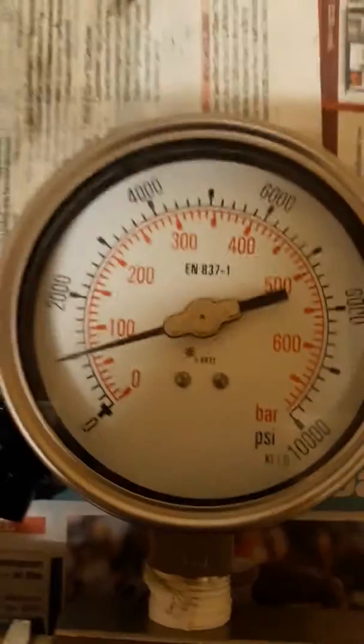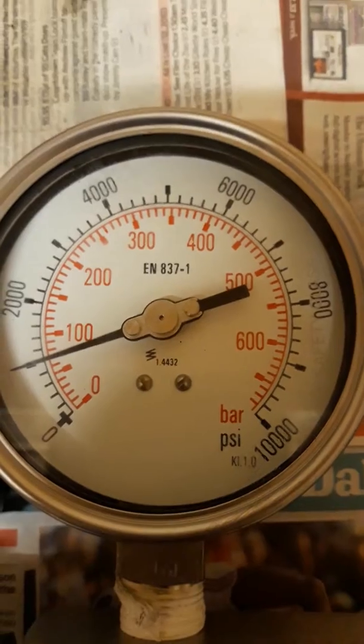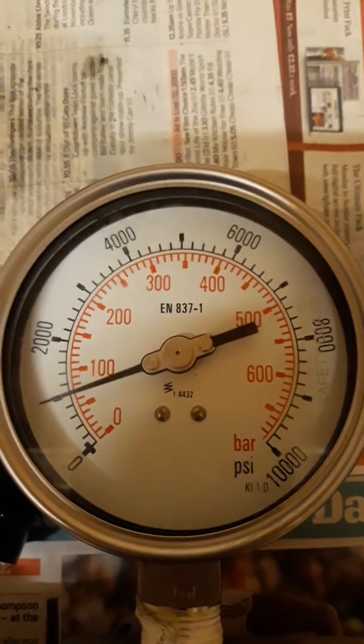We're going to pump it up exactly the same as we did before to see what we get. We'll make sure the valve is closed and start pumping. I can feel resistance in the pump, and you can see this time — I'm still pumping — but we have reached 500 bar on this gauge. I think we can call that a good result.